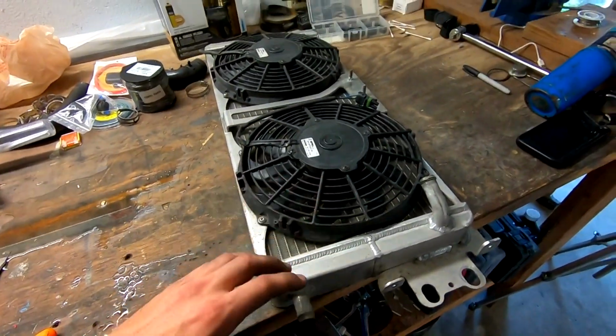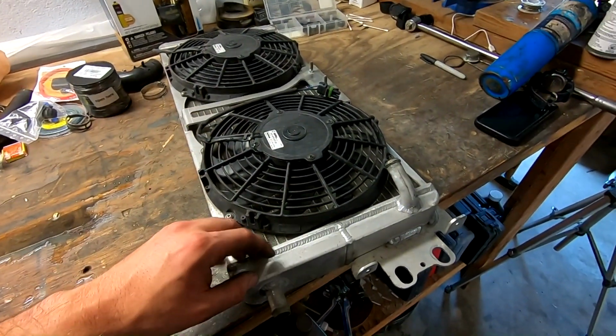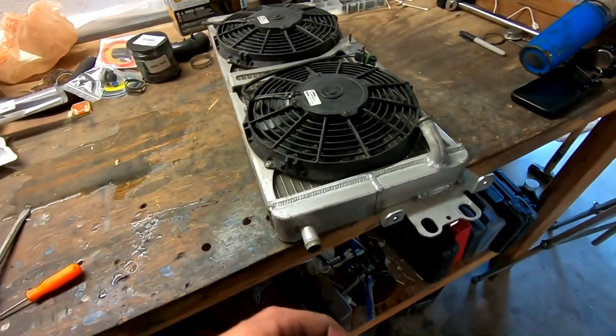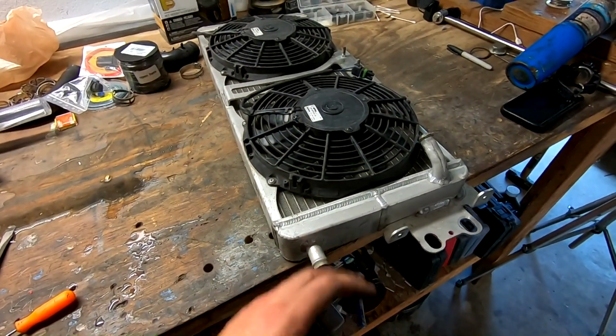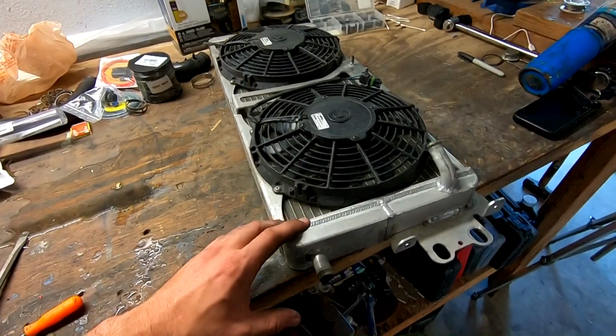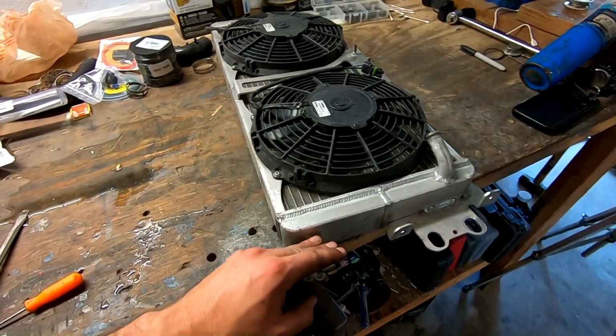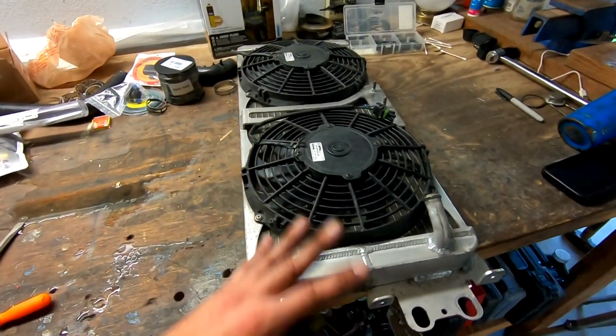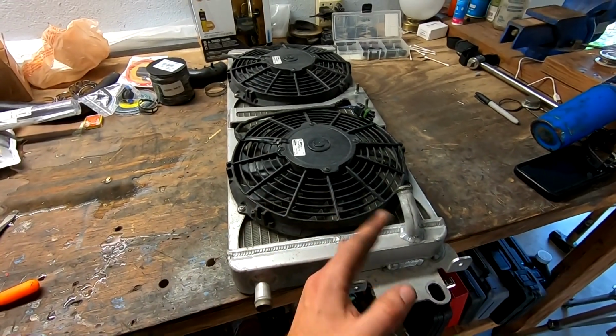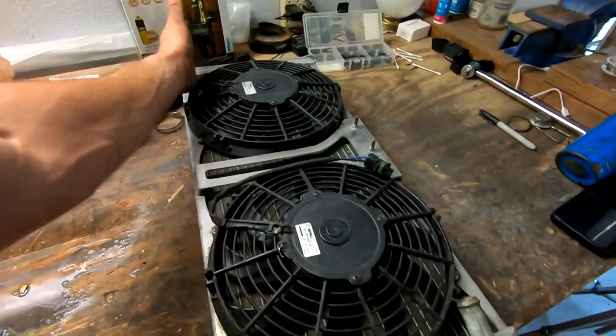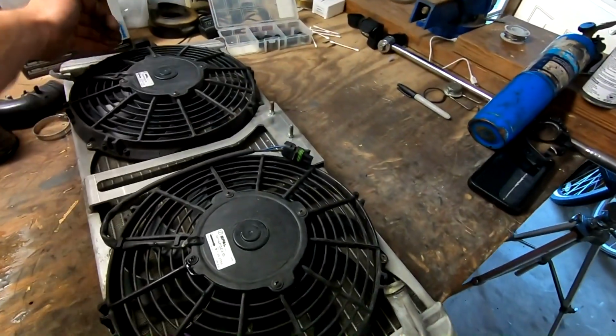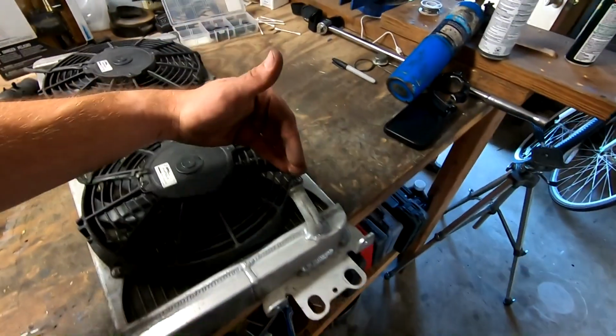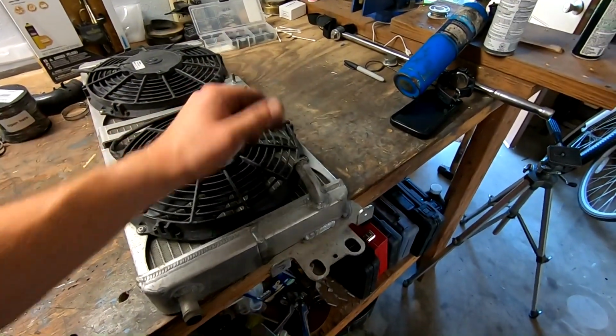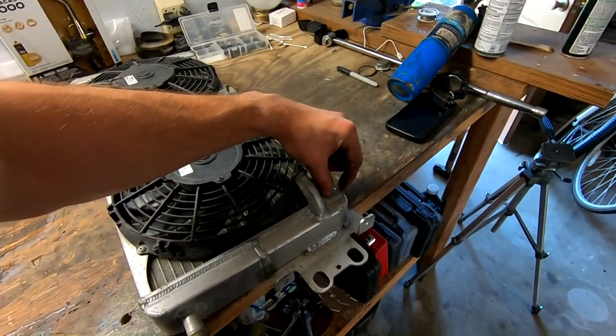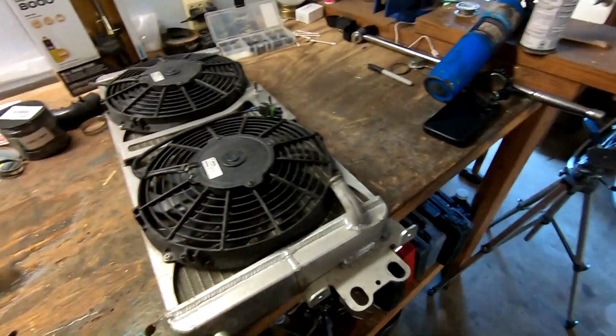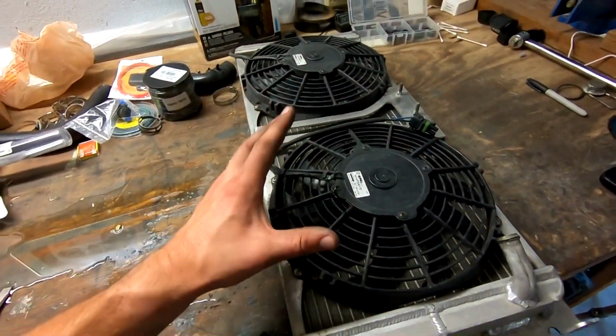That's primarily why I'm concerned about running the lines this way. So instead, I'm going to make sure we have our inlet on the bottom, and any future heat exchanger install should be done this way. Inlet on the bottom so I can push air out and fill water all the way to the top of this line, filling up the whole core. All the air goes to the top, and we should get most of the air out. There's probably still going to be a little air trapped along the top, but it should give a lot better utilization of the core of the heat exchanger.